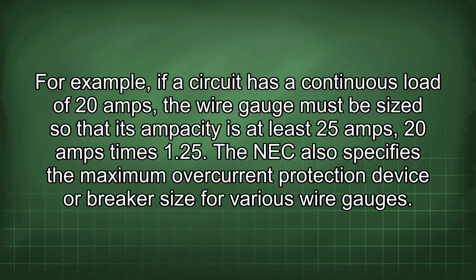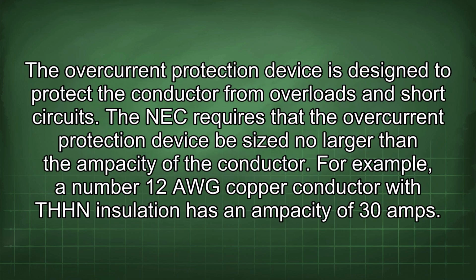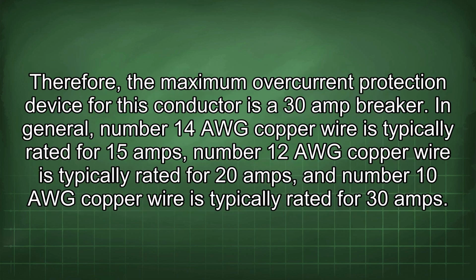The NEC also specifies the maximum overcurrent protection device or breaker size for various wire gauges. The overcurrent protection device is designed to protect the conductor from overloads and short circuits. The NEC requires that the overcurrent protection device be sized no larger than the ampacity of the conductor. For example, a number 12 AWG copper conductor with THHN insulation has an ampacity of 30 amps. Therefore, the maximum overcurrent protection device for this conductor is a 30 amp breaker. In general, number 14 AWG copper wire is typically rated for 15 amps.